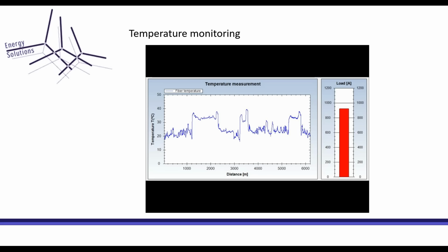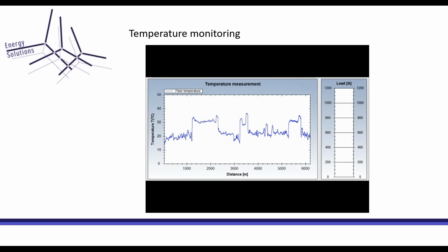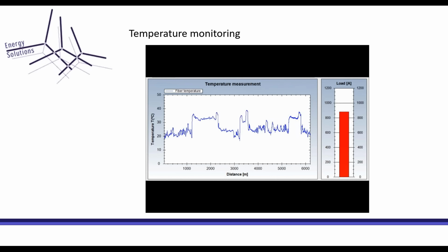This is an example of a load on the cable from a power plant. There are 3 horizontal drillings in the cable. At the end of each horizontal drilling, there is a peak in temperature, and that's because the rest of the drilling is filled with water, but at the end there are some air pockets, and these are quite important also to take into account, because these can be a limiting factor in the cable connection.